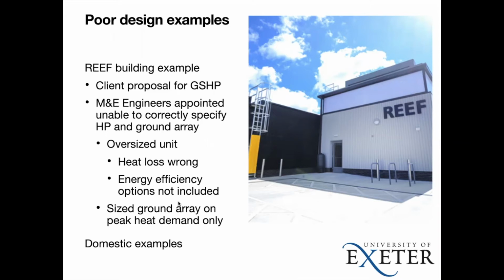It was shocking, really, how poor their design of what should have been a very simple heat pump system was. Effectively, they were using crude calculations that they would typically do for sizing a gas boiler to specify a heat pump, so it was grossly oversized for the heat demand of the building.